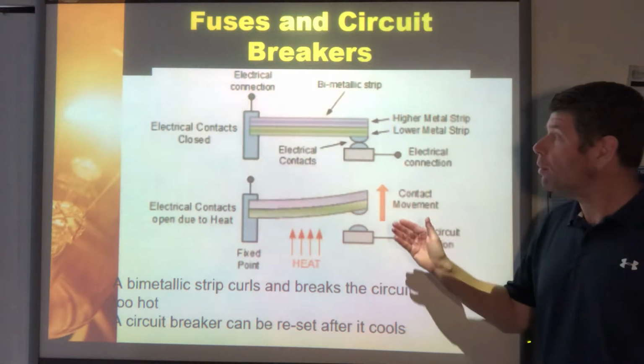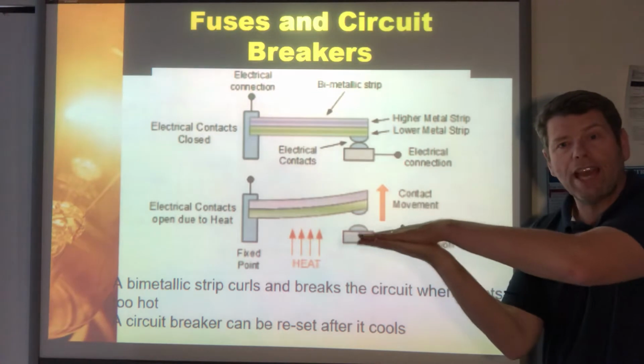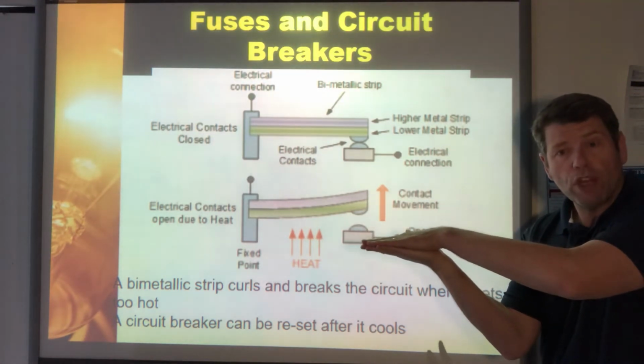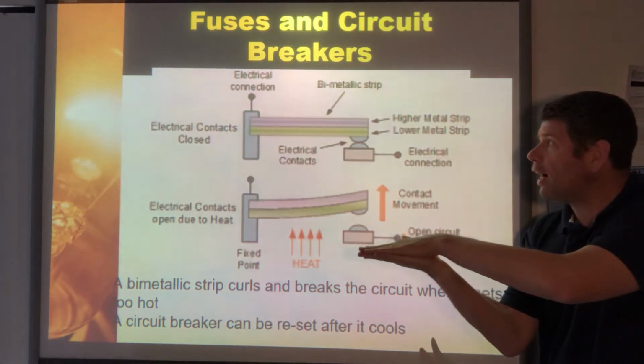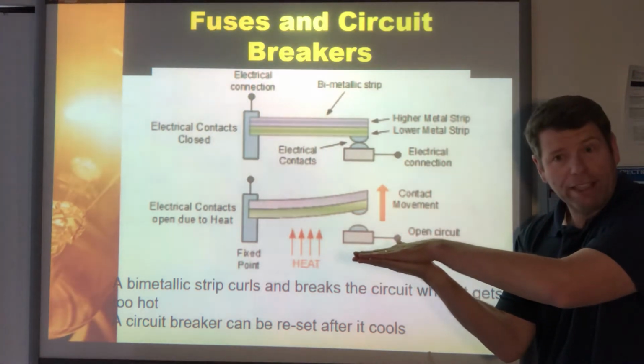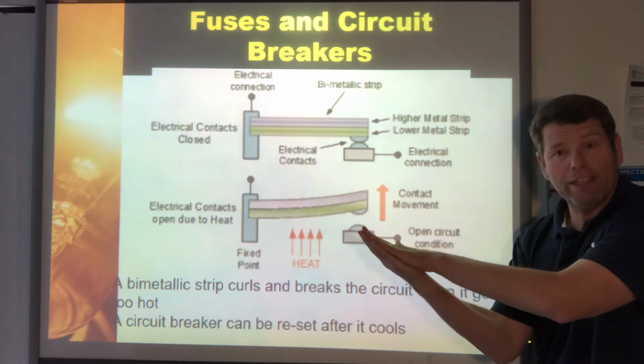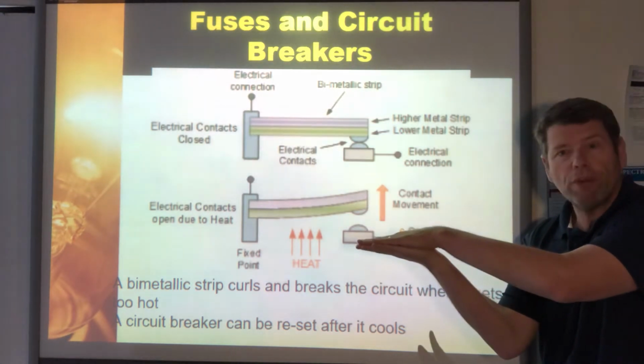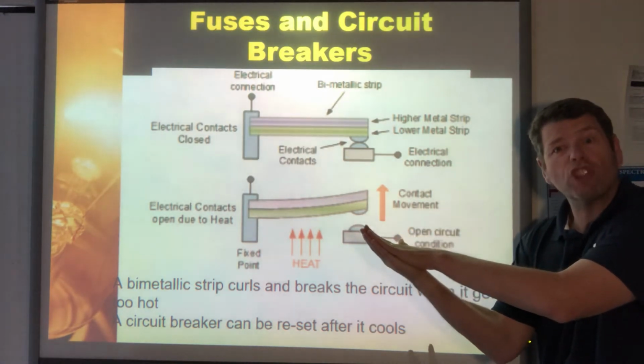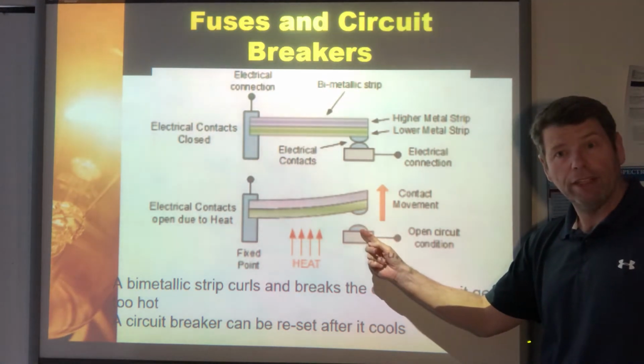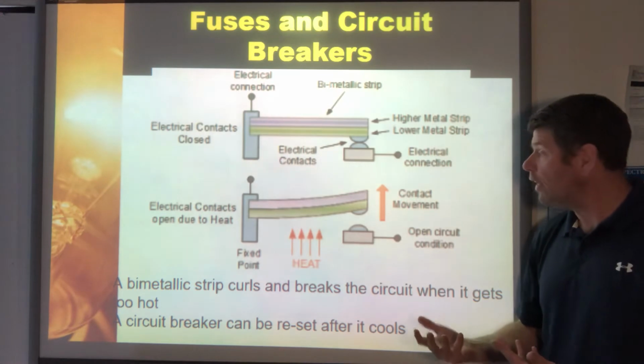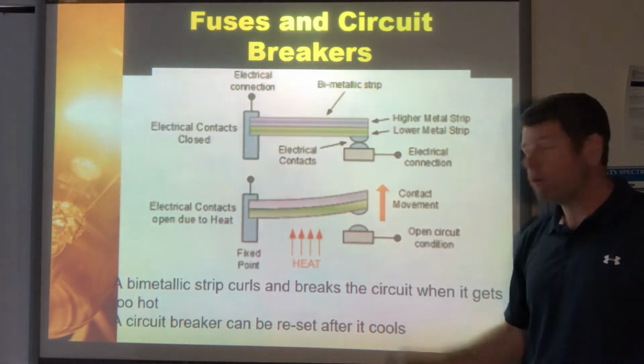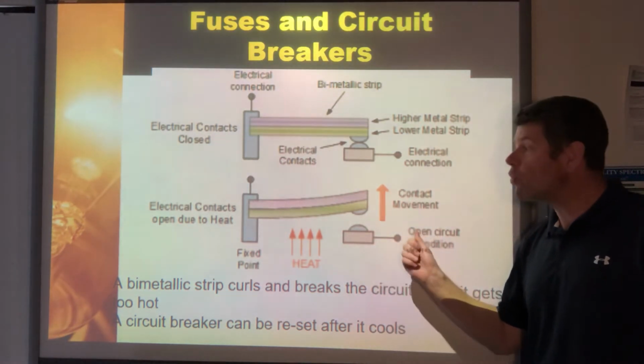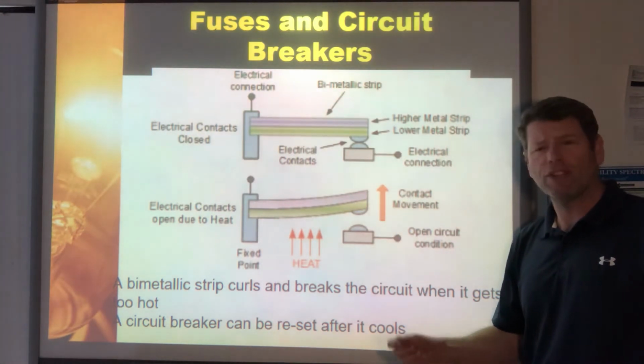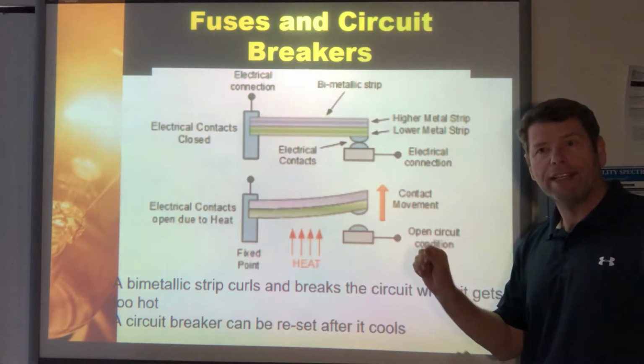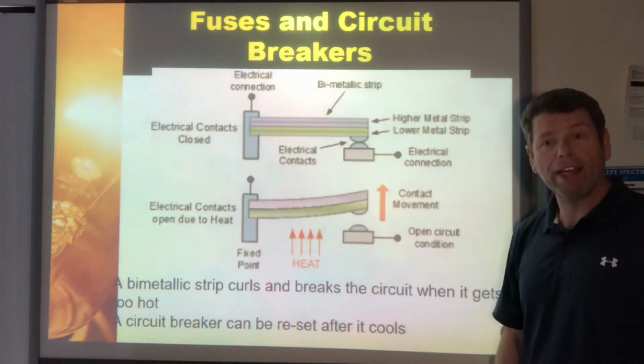A circuit breaker works using a bimetallic strip—two metals bonded together. Just like the thin wire in a fuse, if too much current runs through the bimetallic strip, it gets hot. But instead of melting, it starts to bend because the metal expands as it heats, and since the two metals expand at different rates, that causes the strip to curl. The curling action breaks the circuit, protecting it from too much current. The beauty of a circuit breaker is that once it cools, which happens quite quickly, you can reset it—just move the breaker switch all the way over and then back, and your circuit is ready to go again, without having to keep replacing fuses.